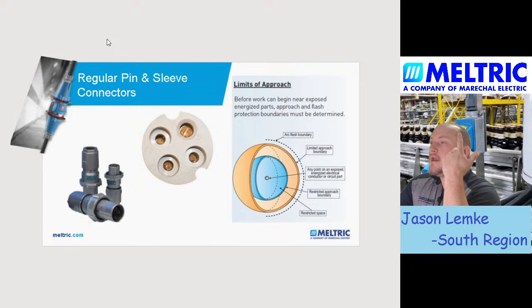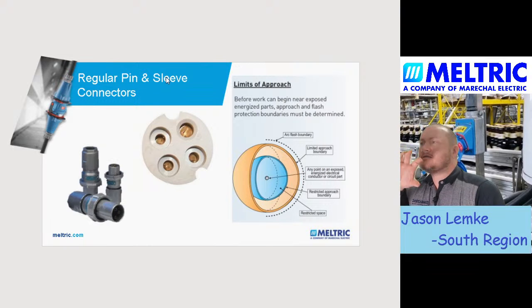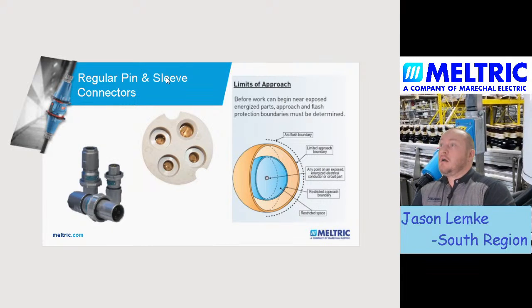You have to have the appropriately rated PPE for whatever your exposure is to arc flash. You potentially have to have PPE for shock exposure as well, for electrical shock. So when you have those pin and sleeve type devices, make sure you're aware of this. I'm not saying you can't use a pin and sleeve device. I'm just saying you have to be aware of what the safety standards are telling you that you should do when you're utilizing these types of devices. There are pin and sleeve devices all over the place in the field. I just see, in my experience, a lot of people using them improperly.